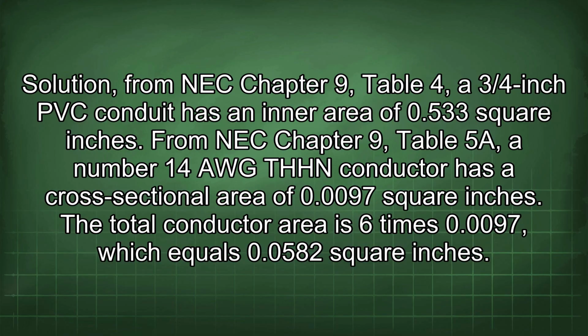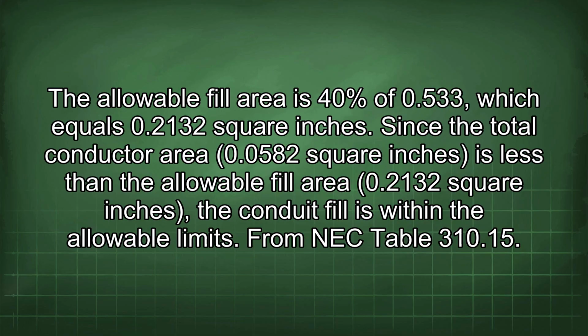The total conductor area is 6 times 0.0097, which equals 0.0582 square inches. The allowable fill area is 40% of 0.533, which equals 0.2132 square inches. Since the total conductor area 0.0582 square inches is less than the allowable fill area 0.2132 square inches, the conduit fill is within the allowable limits.